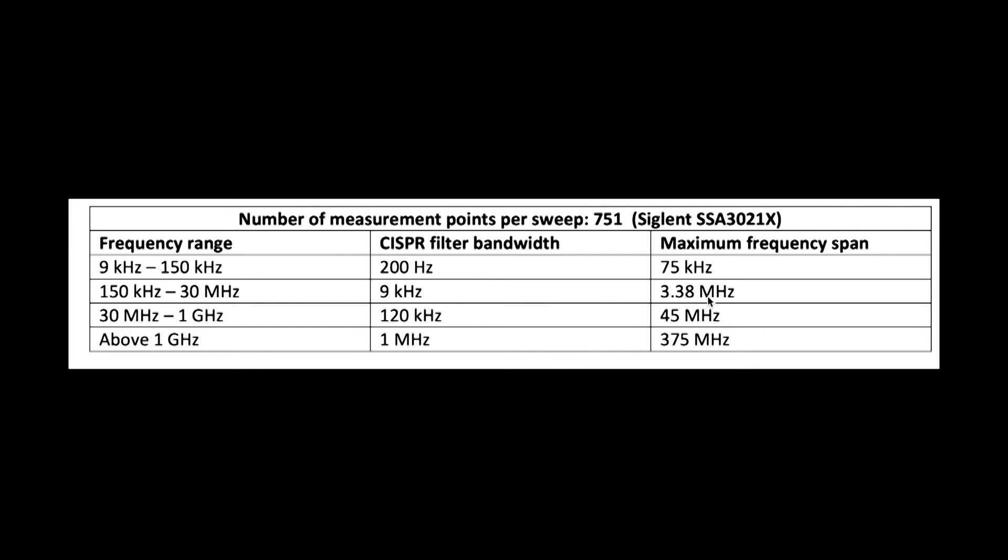In order to cover the entire frequency spectrum, CISPR 16 defines the adjacent frequency points shall not be more than half of the resolution bandwidth. In this case, 9 kilohertz divided by 2 should be 4.5 kilohertz. With this information, we can do the math. As long as we understand our spectrum analyzer model correctly, it shows in this table that for the conducted emission test from 150 kilohertz to 30 megahertz, we will need to split the entire spectrum into at least nine segments with a span of 3.38 megahertz. You can do this test manually, starting at a certain point, scanning for 3.38 megahertz, then starting the next segment, saving all data, extracting those data, and doing post analysis. But having software that does it automatically within five or six minutes saves huge amounts of time and effort. That's why I tend to use software for EMC pre-compliance testing.